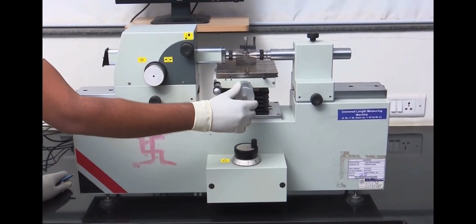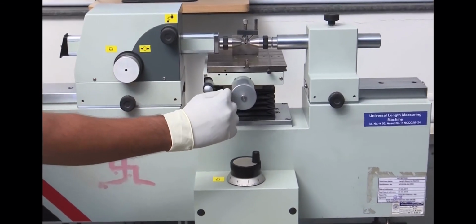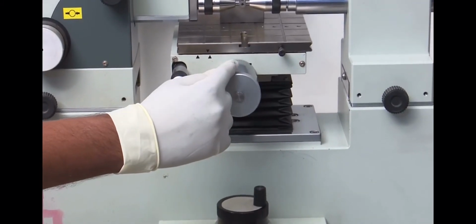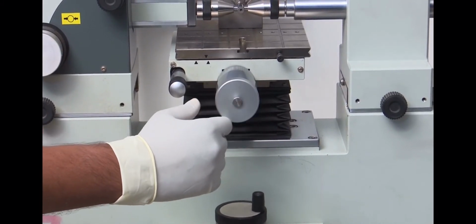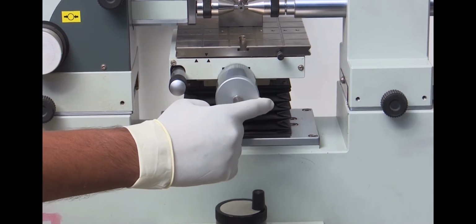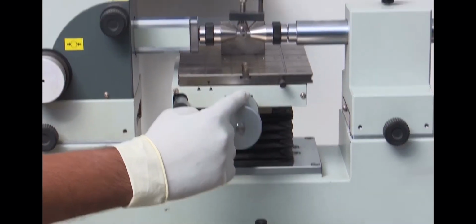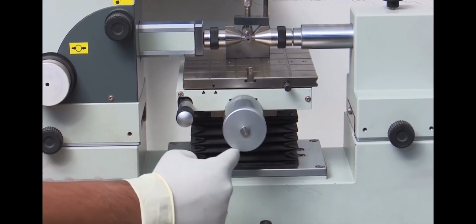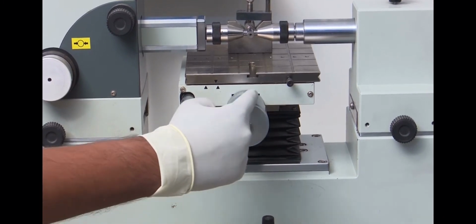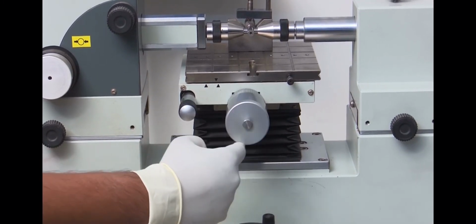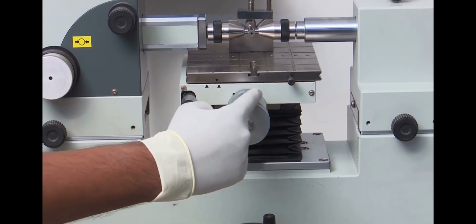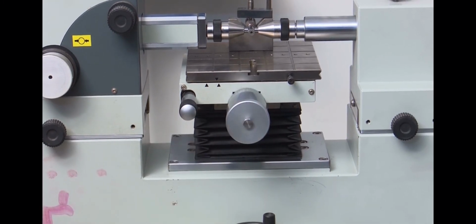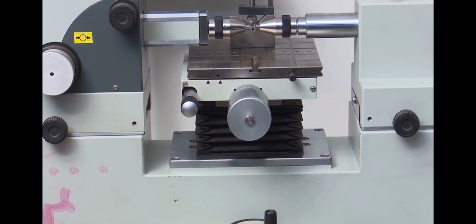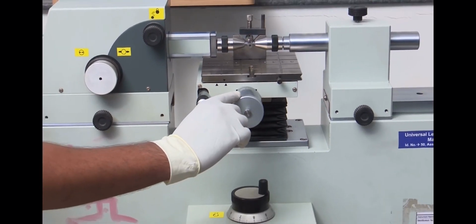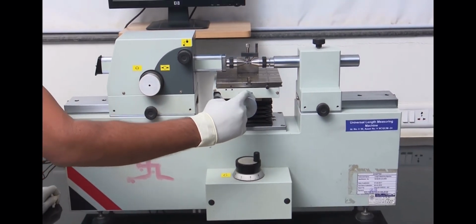Similarly, we can perform calibration at other 4 positions covering the whole surface of plain plug gauge. I have shown you calibration of go end and in the same way we can do calibration of no go end. In this way, the demonstration of calibration of plain plug gauge at one location is completed for this training purpose. You have to perform calibration as per the method.